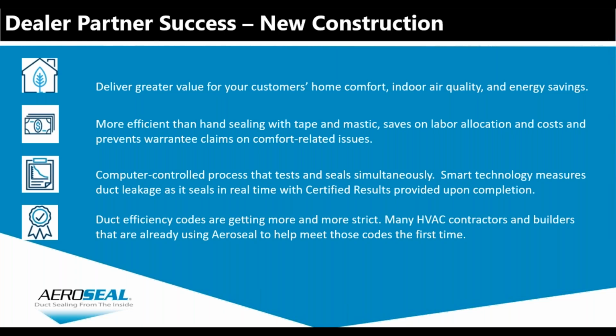So third here, on the computer controlled process, it tests and seals simultaneously. It's smart technology, and it measures the duct leakage as it seals. It's a duct blaster. It's going to be able to show it in real time with certified results upon completion.